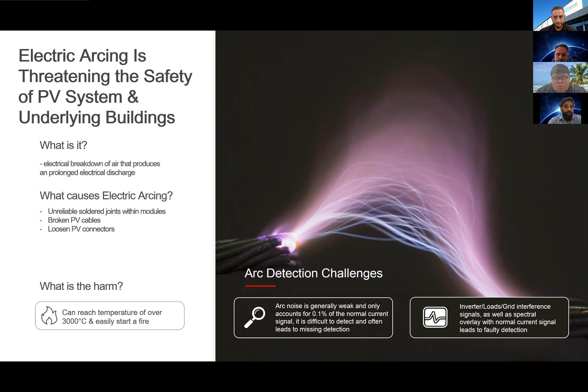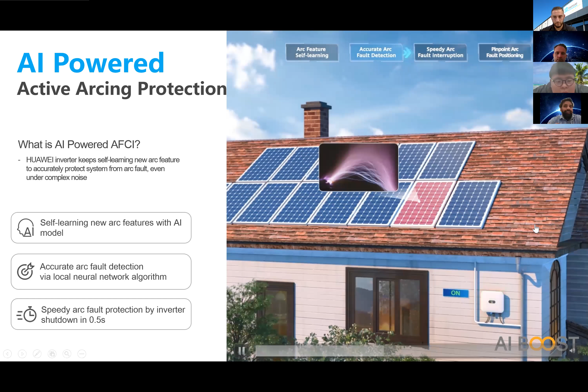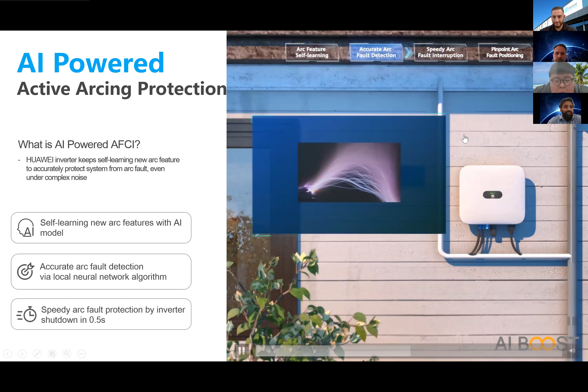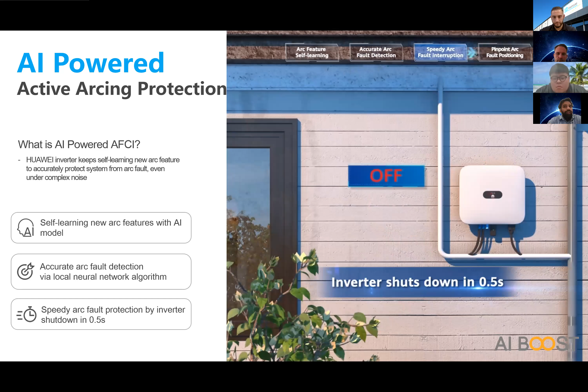What do you expect from an ICT company who has a big AI and cloud business unit? We share the same resources to use artificial intelligence to solve this problem. More than 1 million data sets of frequency spectrum arcs simulated and fed into the algorithm, and the inverter self learns. So frequent firmware upgrades. So in this scenario, in this video, the inverter has detected an AC overlay, converts this into a frequency spectrum, and compares it to the algorithm. If it matches the shape of an arc, then it shuts down in less than 0.5 seconds.